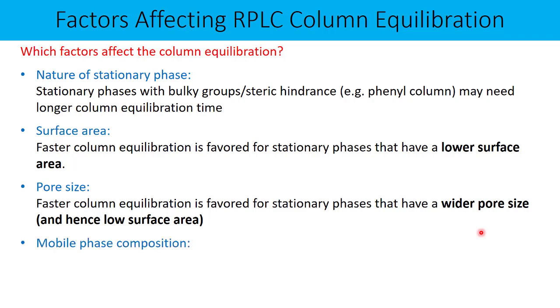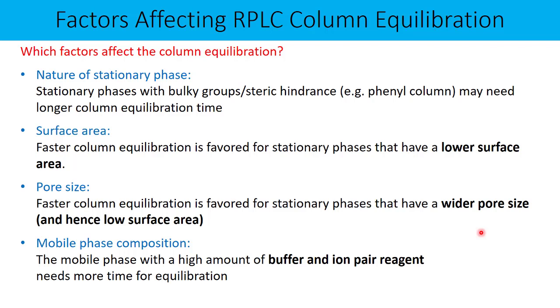What is the role of mobile phase composition? A mobile phase with a high amount of buffer and ion pair reagent needs more time for column equilibration, because more time is required to establish equilibrium between the stationary phase and the mobile phase due to the buffer concentration. Especially if there is an ion pair reagent present, it also has to get equilibrated onto the stationary phase, which may take longer. So one must consider additional column equilibration time especially in ion pairing reagent methods.